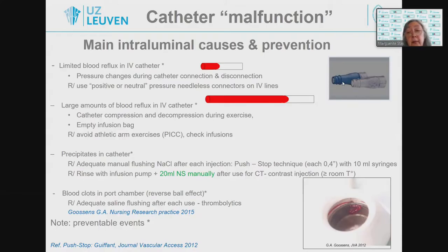You see a picture on the right lower side of this slide: blood clots in the port chamber, and that can be the reason of a strange inconvenience, the reverse ball valve effect, where the aspiration of blood is possible but not the injection of liquids, and therefore you have to use thrombolytics to solve the problem. Please note that most of these events here are preventable.